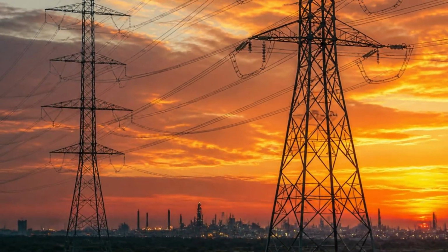Sometimes the governor system can fail because the grid is big. There are other machines elsewhere that are also supposed to be trying to control their frequency, but sometimes, for one reason or another, they can fail, and one power station alone on a big network cannot control the frequency for the whole network. All these machines come into play, they hold hands to make sure they control the frequency. If all these governor systems or any other frequency control systems fail on the network, then eventually that's when protection might come in, either to take the machine off on a lower frequency. You can see a cascade of trips.